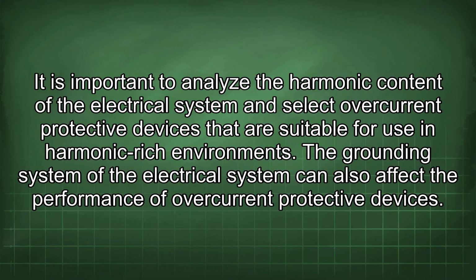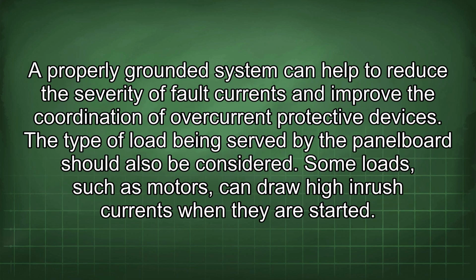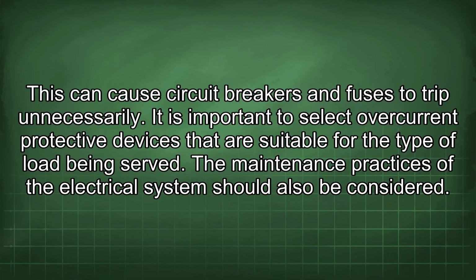The grounding system of the electrical system can also affect the performance of overcurrent protective devices. A properly grounded system can help to reduce the severity of fault currents and improve the coordination of overcurrent protective devices. The type of load being served by the panel board should also be considered. Some loads, such as motors, can draw high inrush currents when they are started. This can cause circuit breakers and fuses to trip unnecessarily. It is important to select overcurrent protective devices that are suitable for the type of load being served.